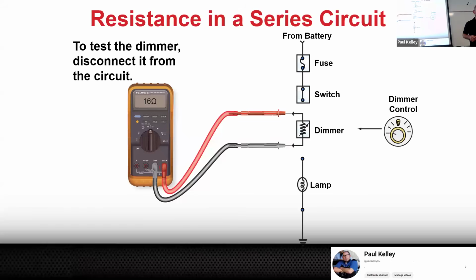All right, another way you could test that. Let's just say, remember that dimmer was damaged by the two-legged varmint. You could measure the resistance of that wire. The resistance of that wire should be about 0 ohms. If you measure resistance of a wire and you get 16 ohms, no wire should have 16 ohms. That's a fail, right?